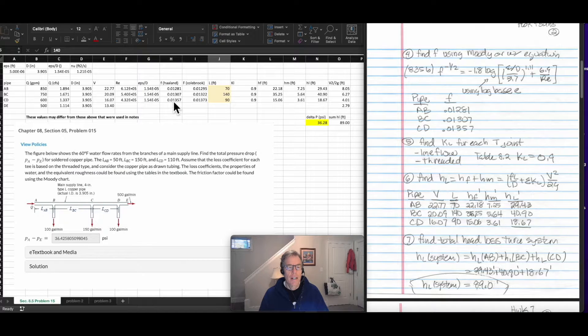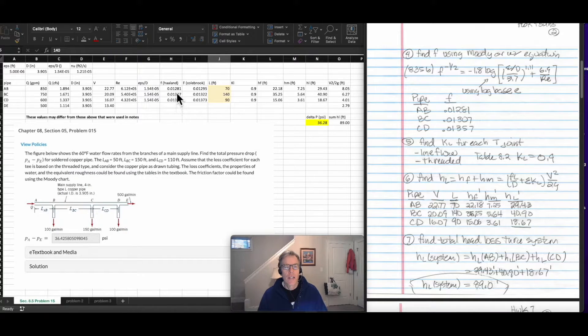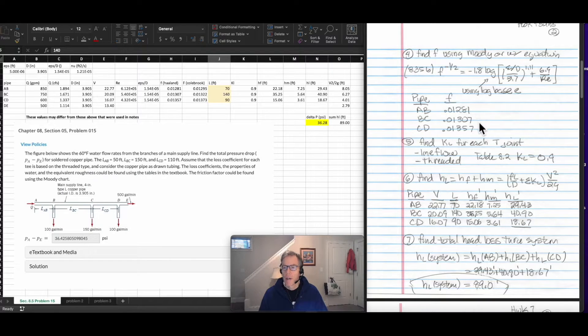I solved the Haaland equation in my Excel spreadsheet, and once I had that calculated friction factor, I then checked it with the Colebrook equation. Since I had an estimate of friction factor along with Reynolds number and relative roughness, I could calculate it with the Colebrook equation. The friction factors from the Haaland equation were quite close to the Colebrook equation results, so I used the Haaland equation values: 0.012813 and 0.01357.